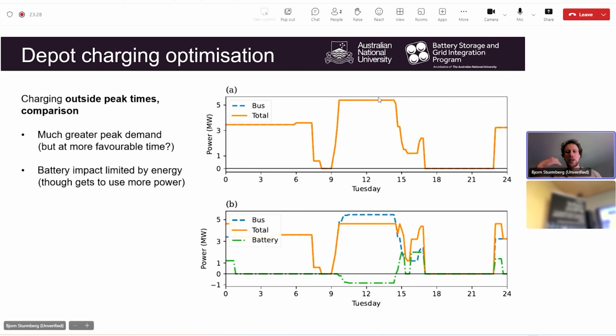Primarily during the middle of the day, we've got to recharge all of your buses that have been out on the morning peak, in preparation for the afternoon peak, that's the afternoon peak hour route schedules, but also to get you through the evening when you're not allowed to charge the buses back at the depot. So that's a huge increase in the power placed on the distribution network, and something that may very well lead to either new or increased upgrade works that would be required at the point of connection of the bus depot, something for which the bus operator will be liable to at least contribute towards.